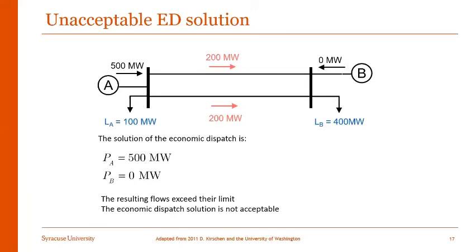Considering that the line limits were 150 megawatts, we see that the resulting flows exceed their limits. In this case, the economic dispatch solution is not acceptable. This is because you can only overload lines to a certain extent. If you keep on overloading lines for a long time, they will sag and might cause failures. Once a line fails, it might cascade to multiple line failures, and we don't want to end up in that situation.